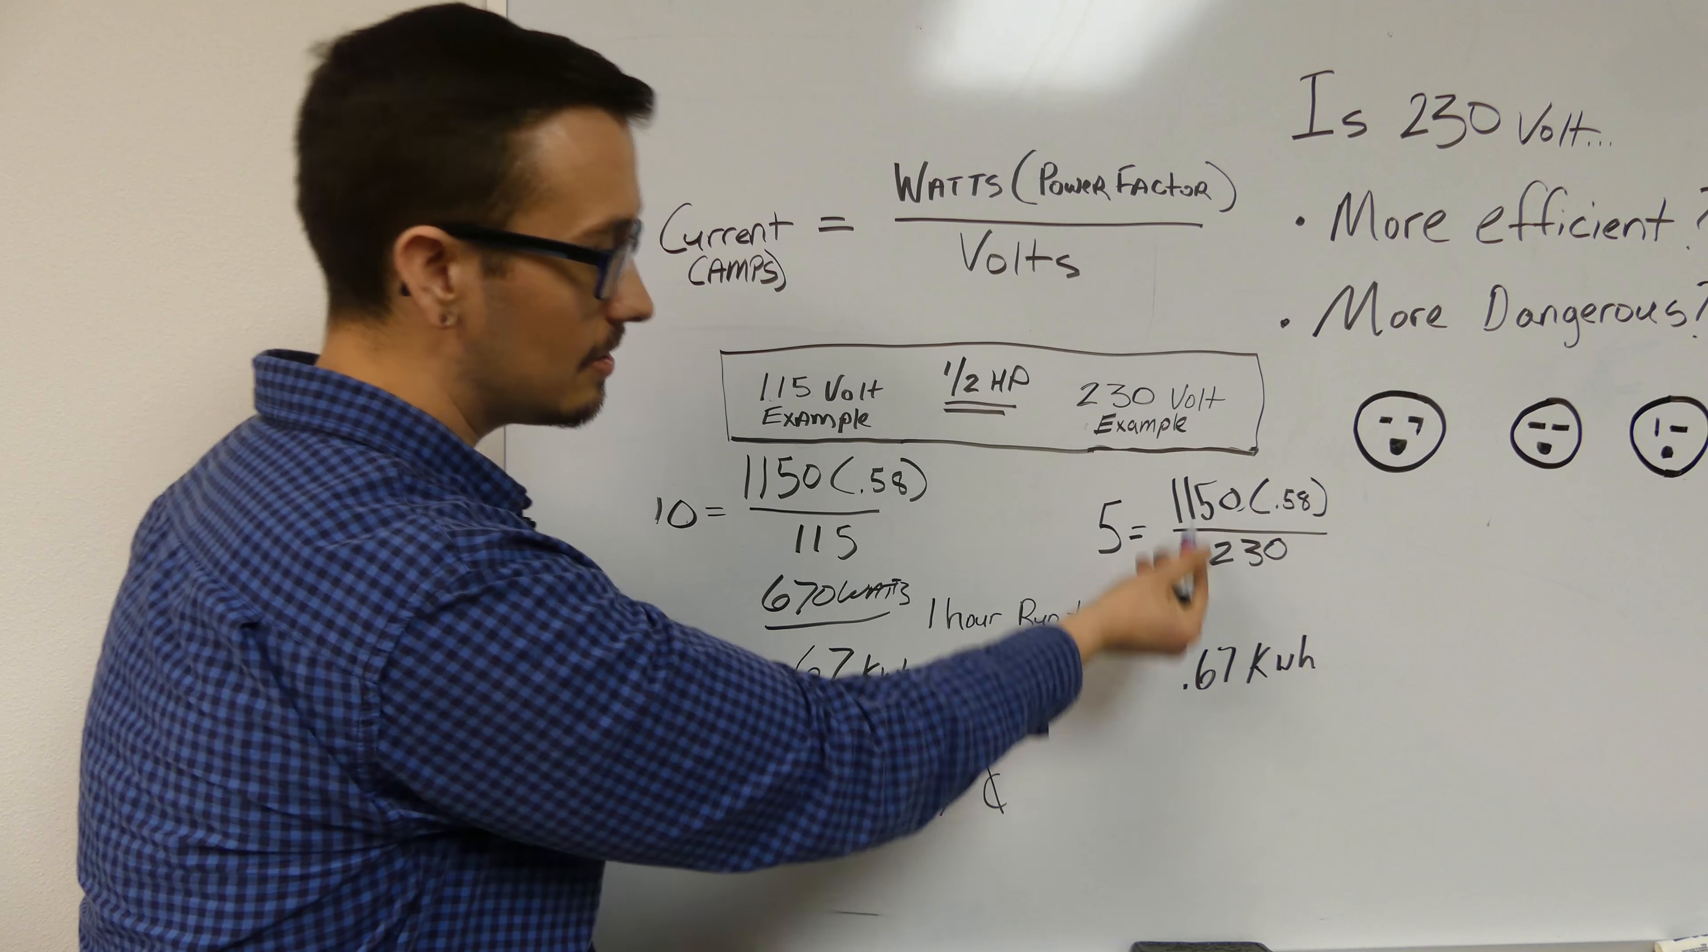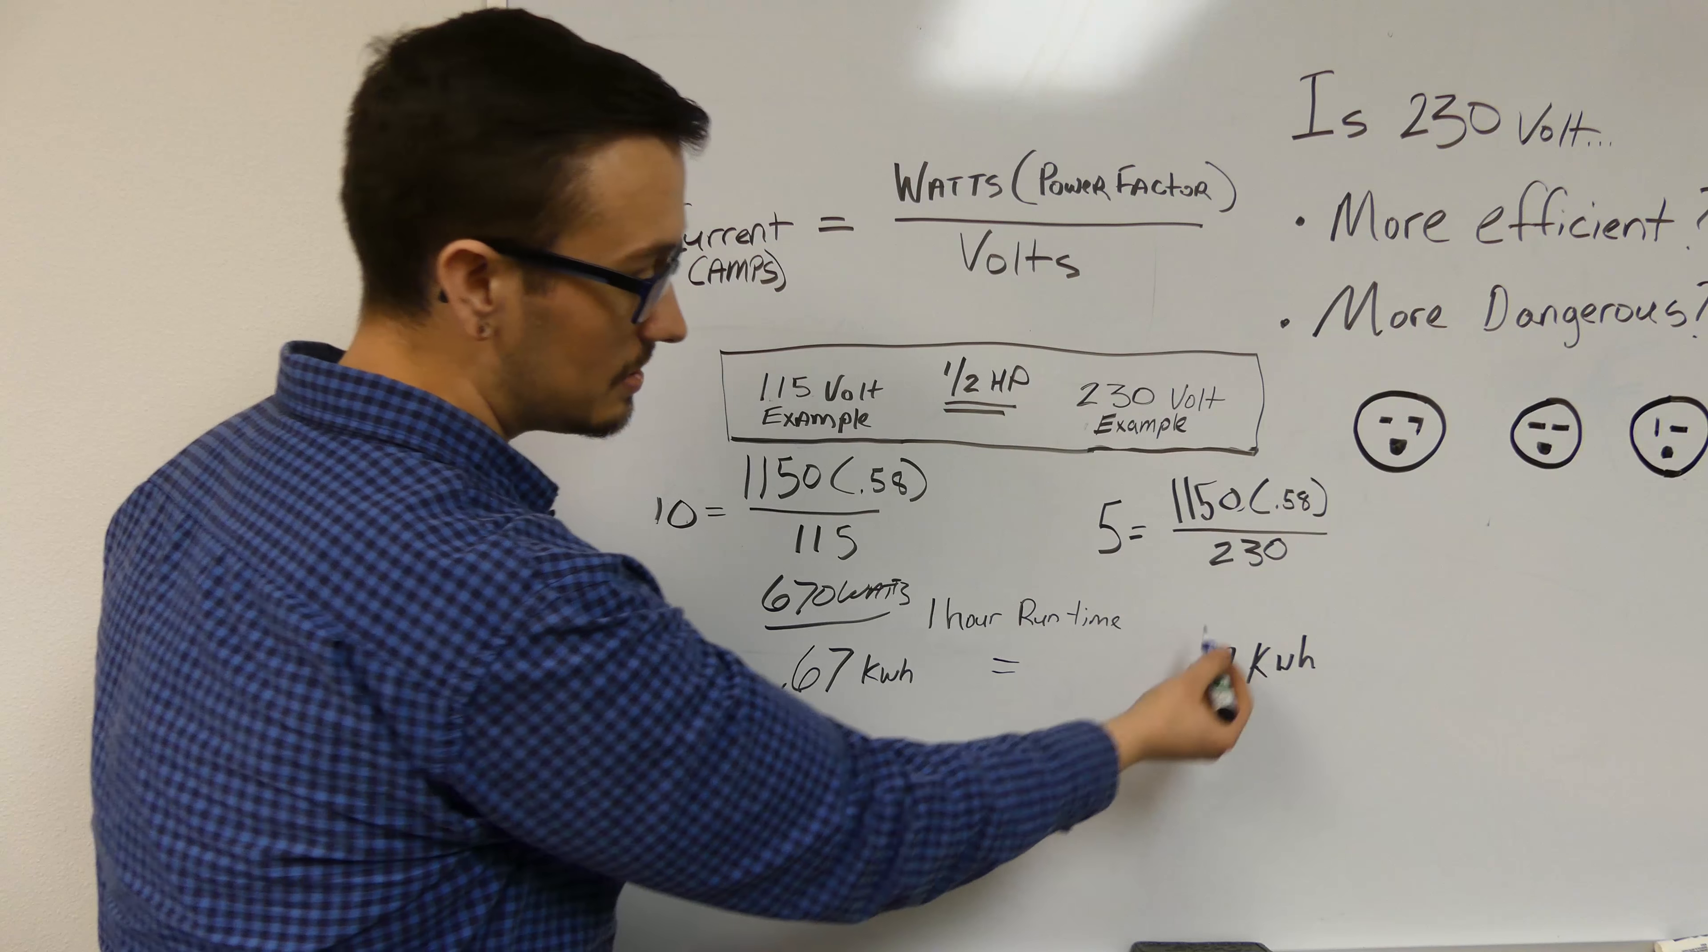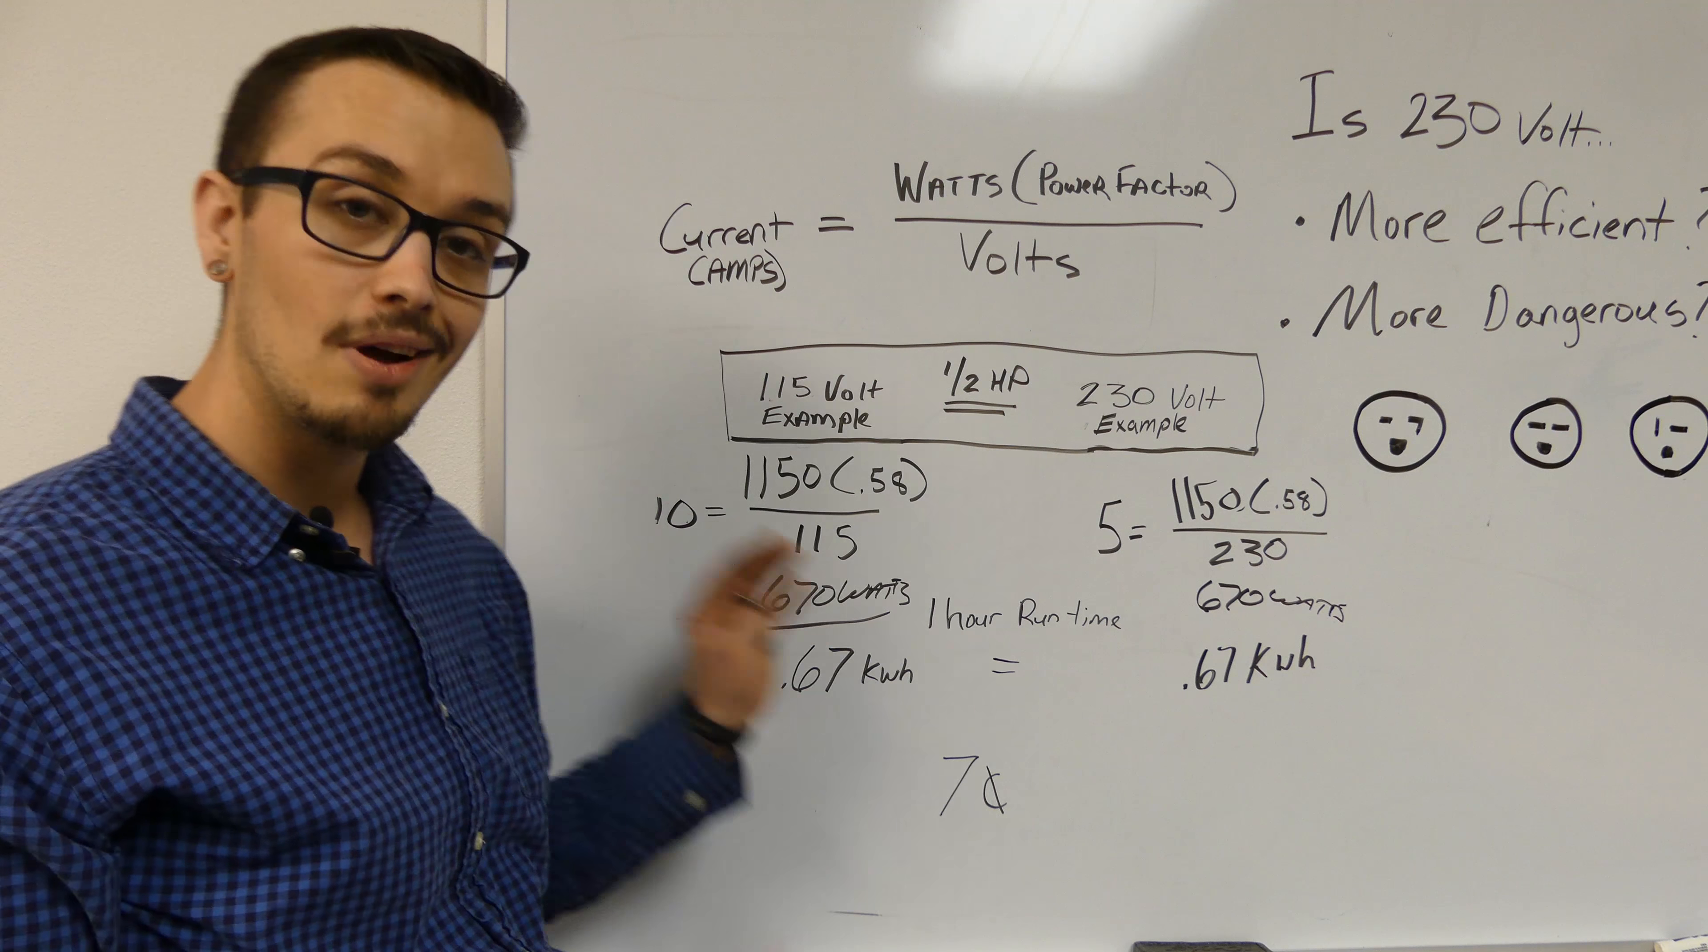Now we run through this whole situation at 230 volt. Five times 230 is 1150. 1150 times power factor, which is identical on both of these motors, and we come up with the same figure: 670 watts.